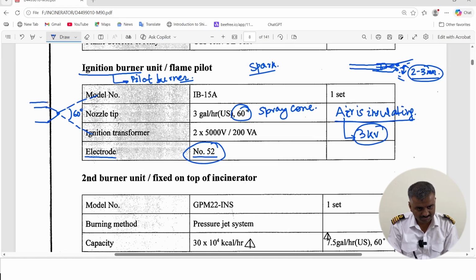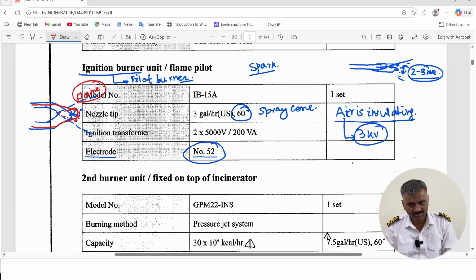Now if you place the electrodes very near to each other, the density of fuel will be so high that this spark will get extinguished. So you will not get flame. That is why you keep the position of electrodes at a distance of approximately 2 to 3 mm, where the propagating cone or the velocity of this atomized fuel is not that much. The spray is in fine mist form and the spark is also present, so the flame will be stable here. That is why you need a 2 to 3 mm gap. Now for this, how much voltage? So let us see, the ignition transformer is there, which is a step up transformer.